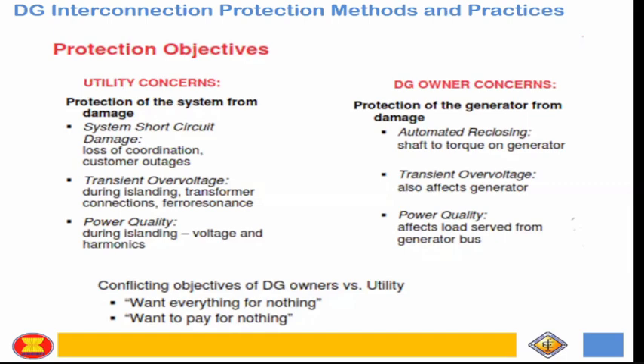And then transient overvoltage also affects the generator. Okay? Because we all know that you cannot operate a generator in an overvoltage scenario, because of the potential overexcitation. Once you operate a generator in overvoltage, the iron core of the generator will also be damaged. So that is also their concern. We also need to supply the generator with the proper voltage. Some generators cannot even synchronize if there is a capacitor bank; they still turn off, de-energize the capacitor bank before the generator synchronizes because of that overvoltage scenario.